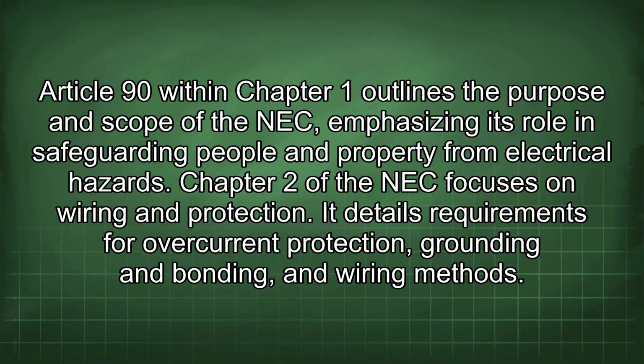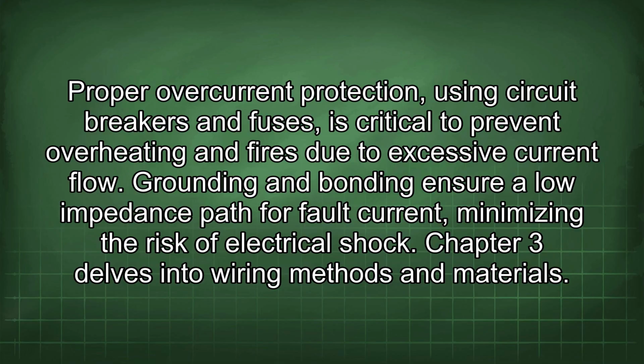Chapter 2 of the NEC focuses on wiring and protection. It details requirements for overcurrent protection, grounding and bonding, and wiring methods. Proper overcurrent protection, using circuit breakers and fuses, is critical to prevent overheating and fires due to excessive current flow. Grounding and bonding ensure a low impedance path for fault current, minimizing the risk of electrical shock.